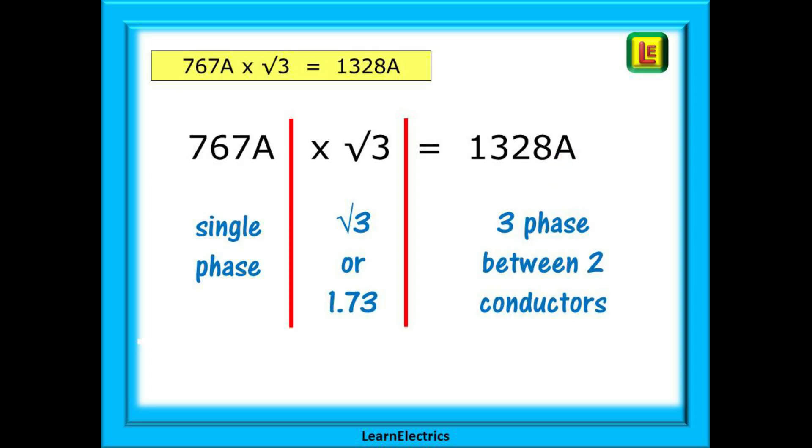The regulations book tells us that to arrive at a three phase fault current, we should multiply the single phase line to neutral current value by root 3. We have just measured what it will be at 230 volts. Now we want to know what the fault current will be at 400 volts. So 767 amps multiplied by root 3, or 1.73, will come to 1328 amps. This is our fault current if there's a short between two phase conductors in a three phase system in this example.